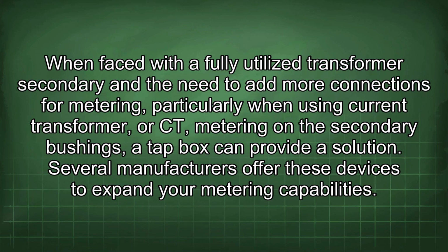When faced with a fully utilized transformer secondary and the need to add more connections for metering, particularly when using current transformer or CT metering on the secondary bushings, a tap box can provide a solution. Several manufacturers offer these devices to expand your metering capabilities.